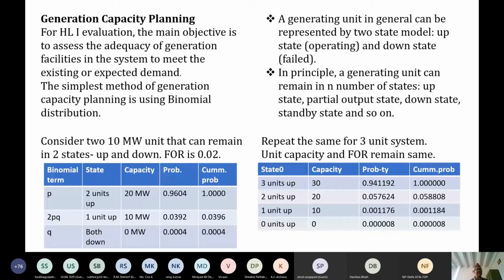Now let us consider two 10 megawatt units that can remain in two states, up and down, and the forced outage rate is 0.02. Usually for generating units, the forced outage rates are in the range of 0.01 to 0.05. If it is a very reliable generating unit, then its forced outage rate will be lower. It can be 0.01. But if it is less reliable, then it can be 0.05, or in some cases it can be 0.1 also. That means 10% of the time we can expect the generating unit not to be in operational condition.